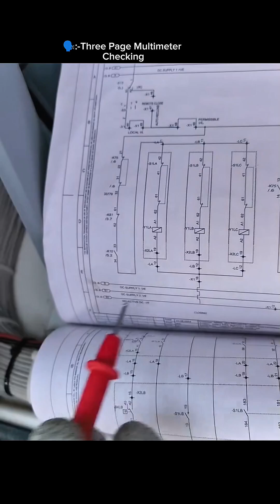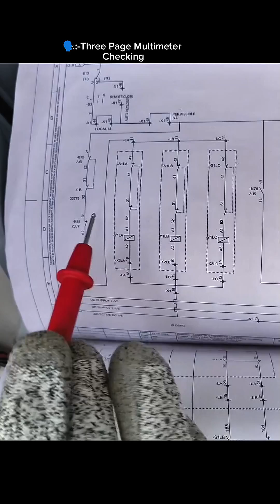Hi guys, now we will check the breaker coil resistance. This is the breaker close coil. This is R phase, this is Y phase, this is B phase. A2 is the negative terminal, A1 is the positive terminal. Now the breaker is in open condition, so we will check the point.